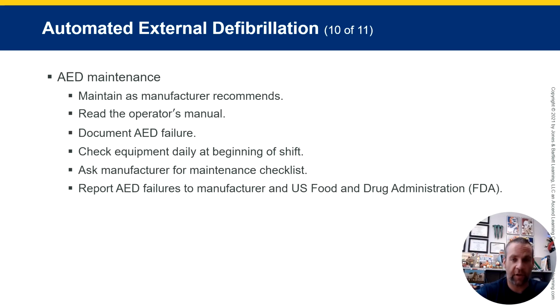Confirm that the batteries are charged. Pads are in date, so they're not expired. They're sealed, and the unit powers on without any errors. If the AED actually fails in the field, it's not just inconvenient; it can actually cost someone's life. Right? So always document any issues and take the unit out of service until it's repaired or replaced.